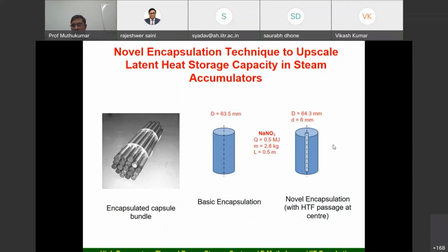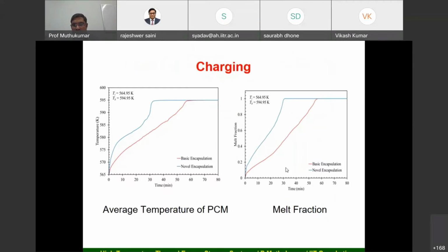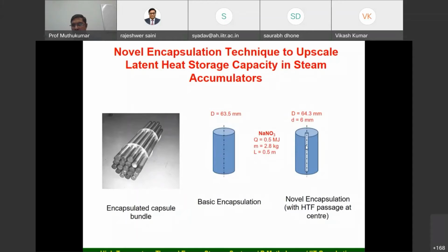Here, we inserted a quarter-inch tube. In both cases, we fill the same amount of material. Since we inserted this small tube, the diameter increased only slightly, less than 1 mm. With this arrangement, we can reduce the charging time by about 30%, and the discharging time by 40 to 50%. Providing a hole at the center reduces the effective thermal resistance of the system, enabling rapid charging and discharging.